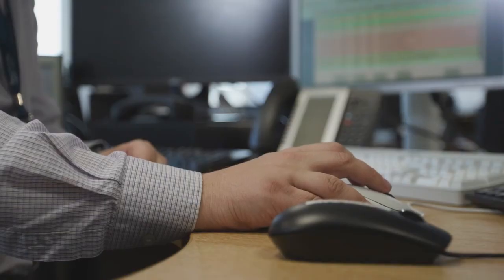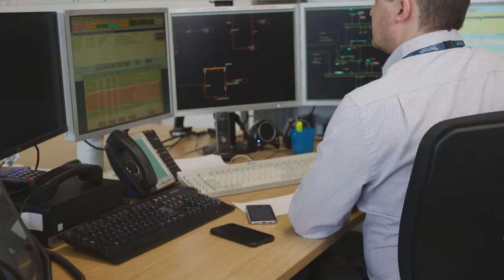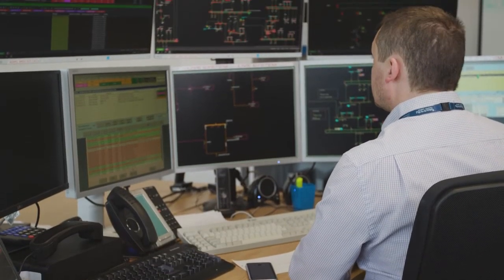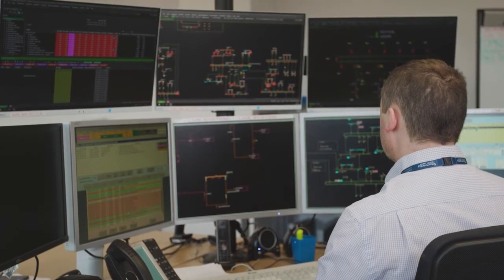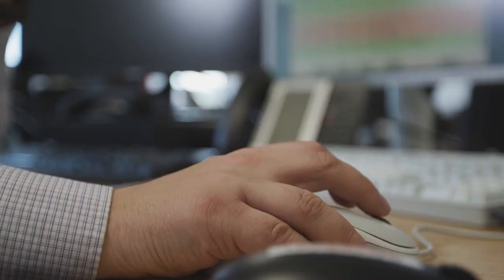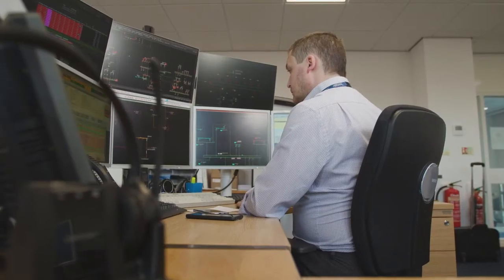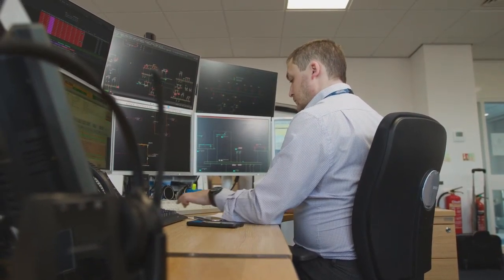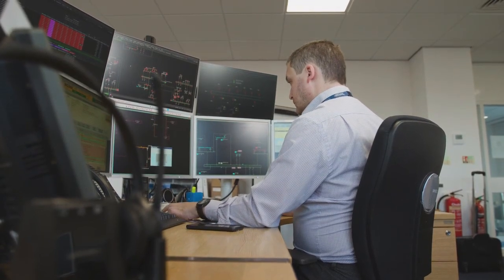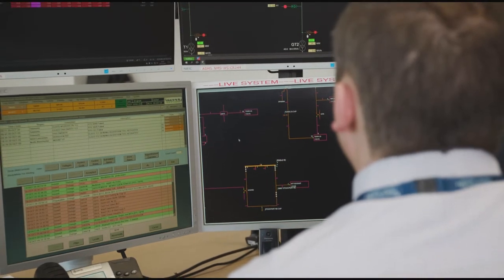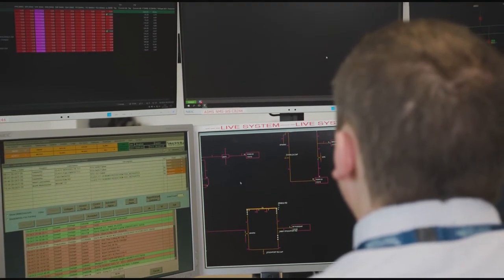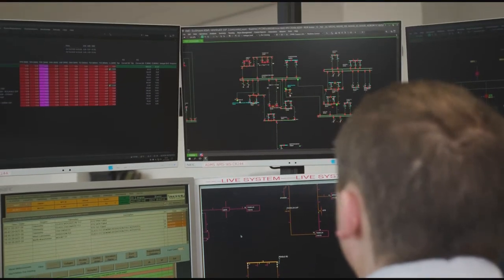in the process of carrying out an upgrade program to resolve the voltage drift issues that we've faced. We've got another 32 installations to carry out. A live dashboard, which is basically a fault tracker, has been developed by Kelvatech as well. This is a web-based system which identifies all the trial circuits, all devices on those circuits, and will identify problems associated with each of the devices. So hopefully we plan to complete the upgrades and installations by at the latest February 2021.